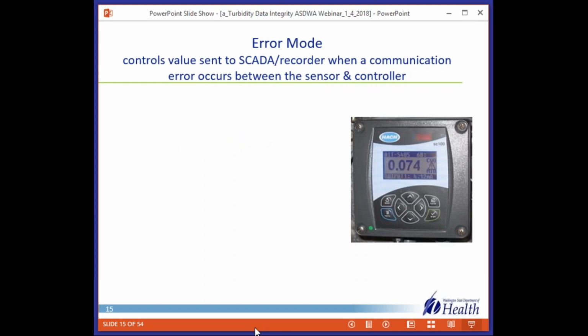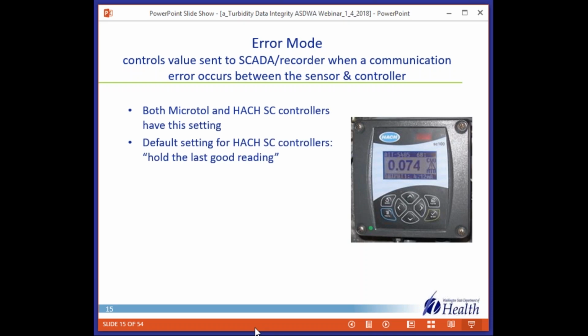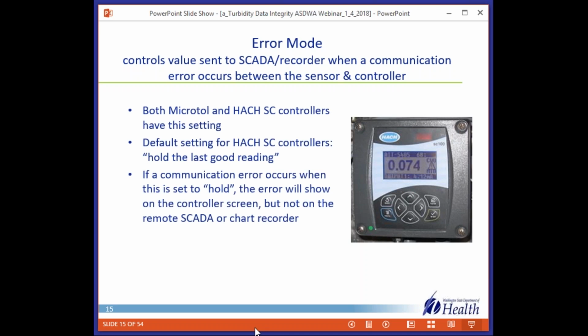The error mode controls the value sent to SCADA or the recorder when a communication error occurs between the sensor and the controller. And there are two options, hold or transfer to a value. Both MicroTOL and SC controllers have the setting. And the default setting for the controllers is hold the last good reading. So with this, if a communication error occurs when it's set to hold, the error will show on the controller screen as shown in this picture, but it will not show on the remote SCADA or chart recorder. So the instrument is no longer sending up-to-date information to the controller, but you don't know that unless you're at the controller in this setting.